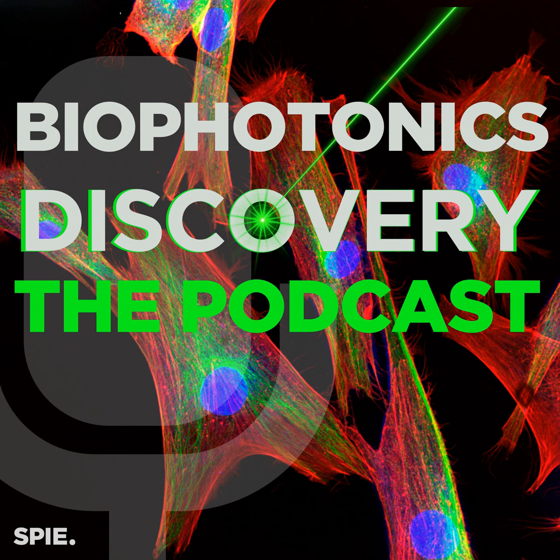And so what we do for this approach is we flood illuminate the fundus or the retina, and all these point sources in the object are mapped to an extended caustic pattern on the detector, and we measure a blur like this. And then we can essentially deconvolve this blur with characterized and measured point spread functions to reconstruct that flood illuminated object, that fundus or retina. And hopefully at the same time, get an eyeglass prescription out of this measurement, in one device, in one measurement.